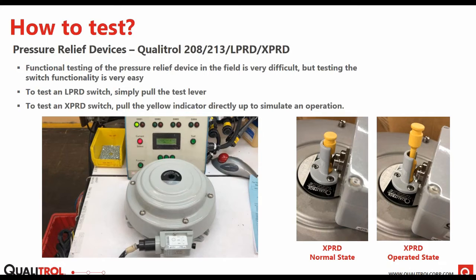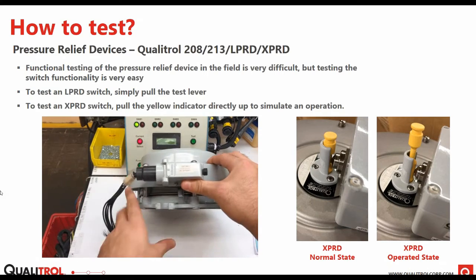But testing the switch is very simple on both of these. And the reason you want to test the switch is because that's typically the most common failure point on these. You're not going to have excessive wear on the springs or seals internally on the pressure relief device. The switch is what is out in the environment. It takes the brunt of the damage and wear and tear. So it's best to test those on a regular basis too. So we can see here a video of the LPRD testing.